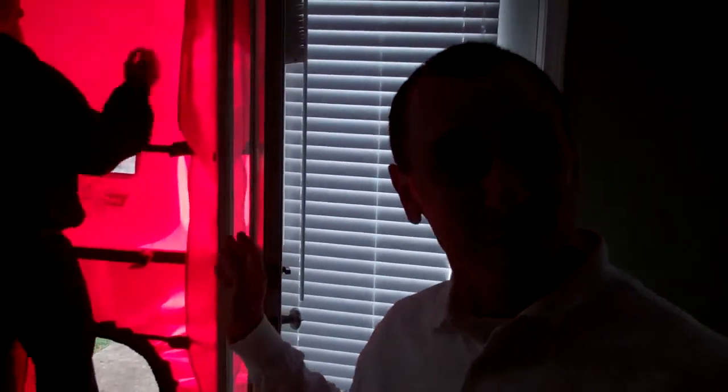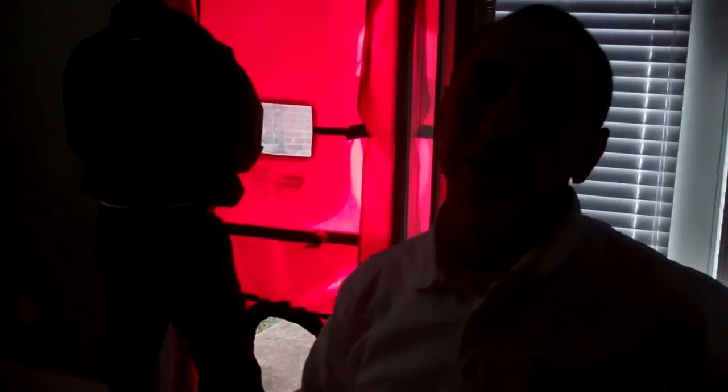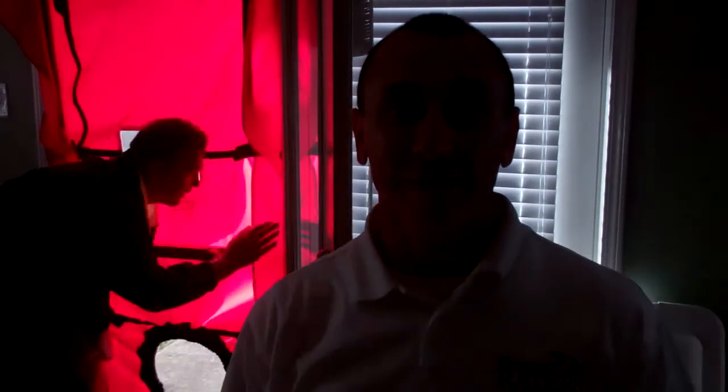We're actually going to do a blower door on this one particular side of the house. But Mr. Tim is going to go ahead. He's setting the curtain up. And what the blower door is going to do for us is test how leaky the house is with respect to the outdoors. And that's a real critical measurement that we want to find out, because if we can get this house tighter, we'll use less energy to condition the air on the inside, be it heating or cooling, depending on the season.